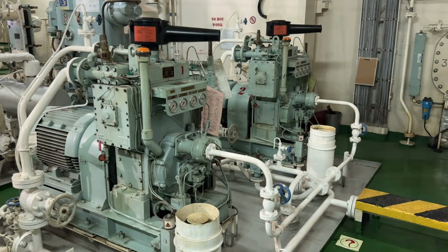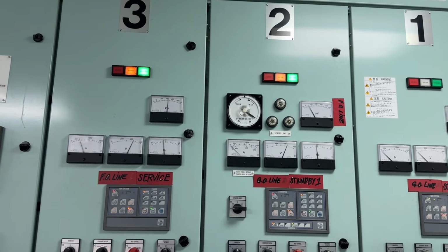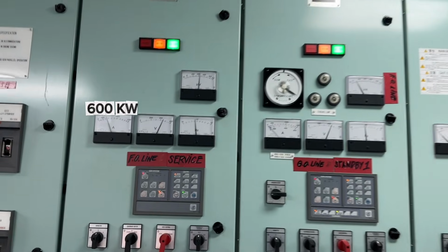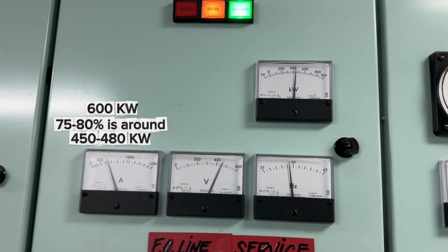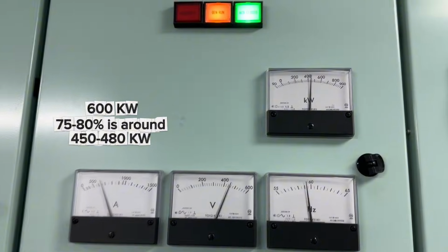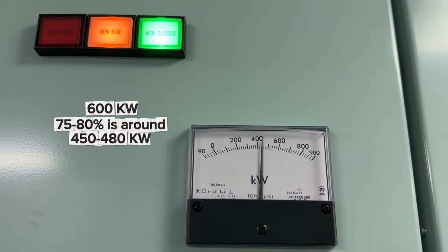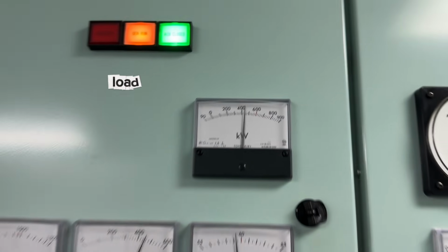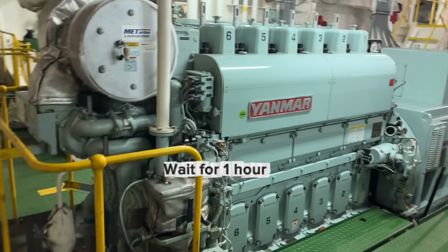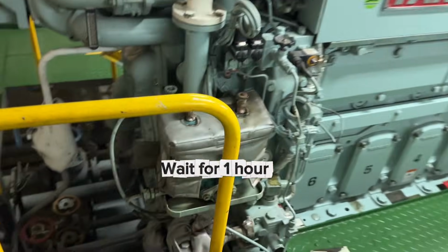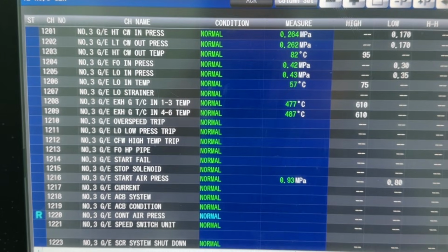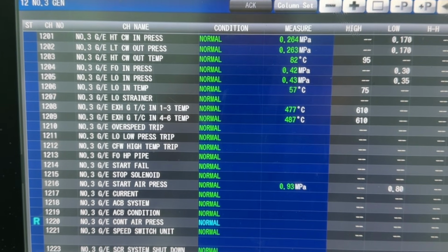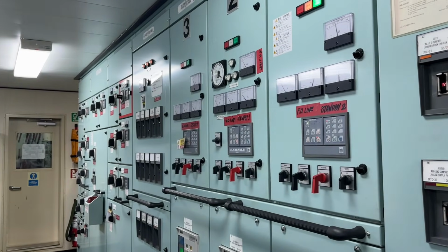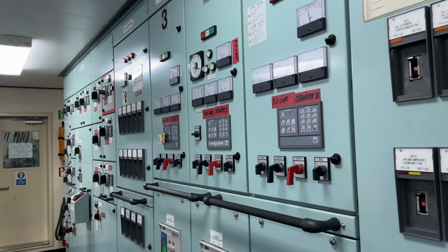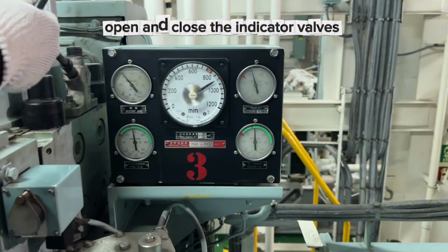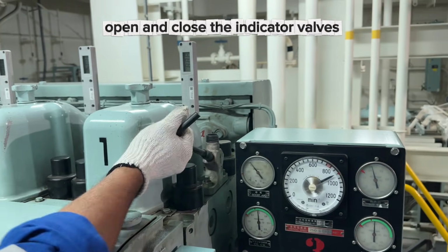For example, if the maximum load or kilowatt of our generator is 600 kilowatts, then 75 to 80% is around 450 to 480 kilowatts. Once the load is stable, wait for 1 hour to perform the performance test and record the parameters, so it allows the parameters to stabilize. After 1 hour, go to the engine side and open and close all indicator valves for testing.